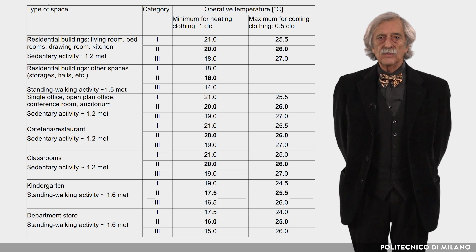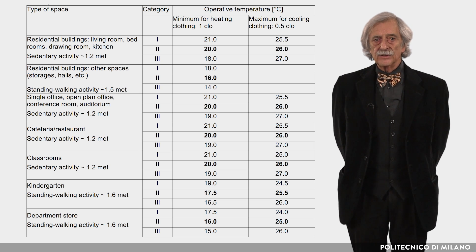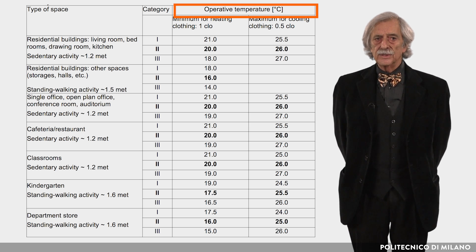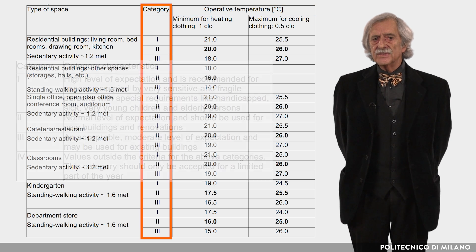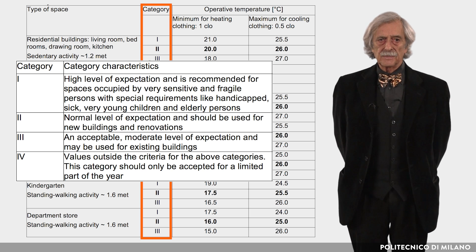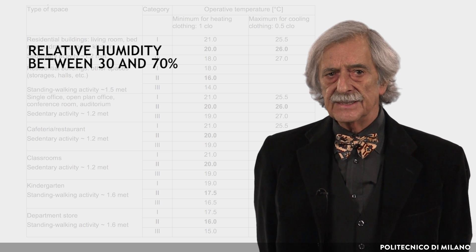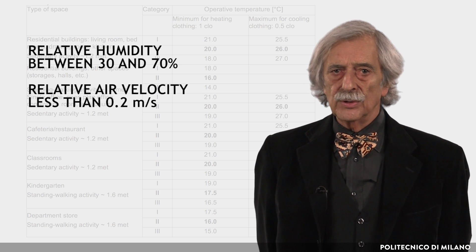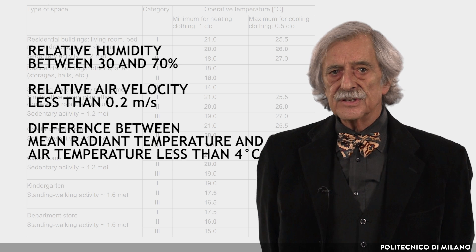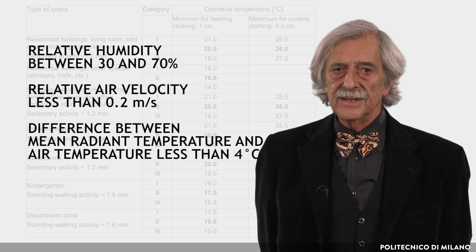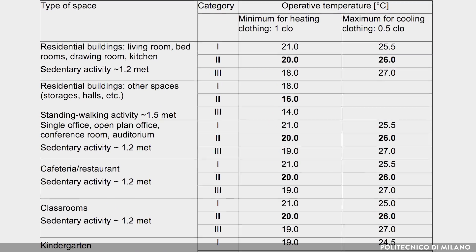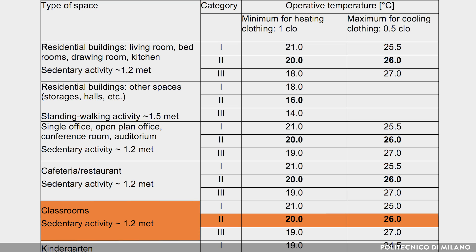To take into account this effect, the European standard EN 15251 on comfort temperatures to be maintained in heated and air-conditioned spaces refers to the operative temperature, not to the air temperature, as shown in the table, where different categories of environmental quality are also considered. The values can be applied if relative humidity is between 30 and 70%, relative air velocity is less than 0.2 m/s, and the difference between mean radiant temperature and air temperature is less than 4°C. For example, in classrooms of category 2 where sedentary activity takes place, the recommended design value of indoor operative temperature for cooling is 26°C.